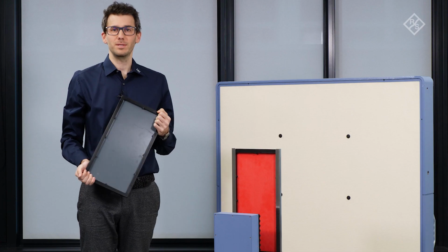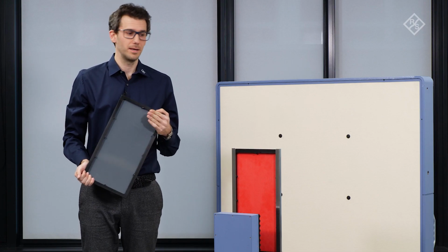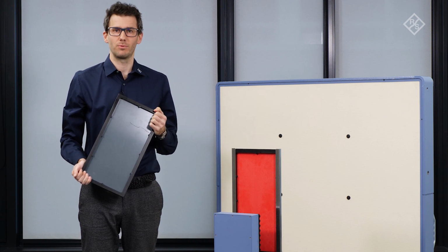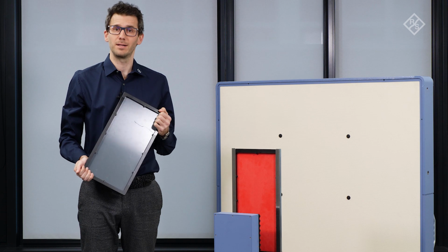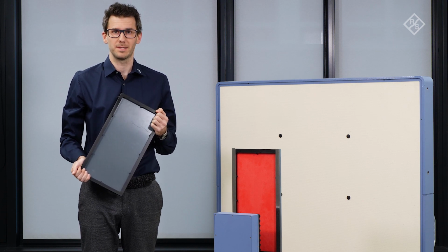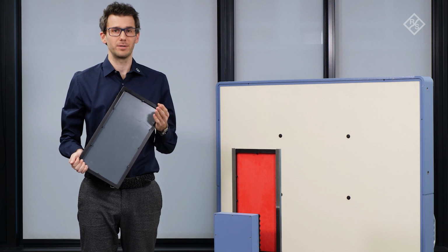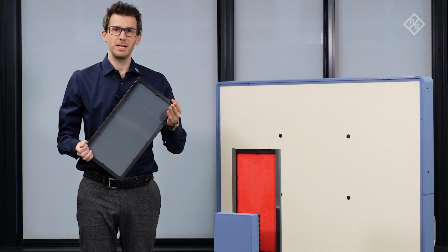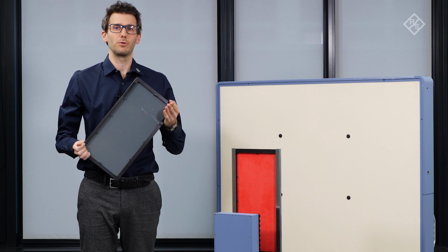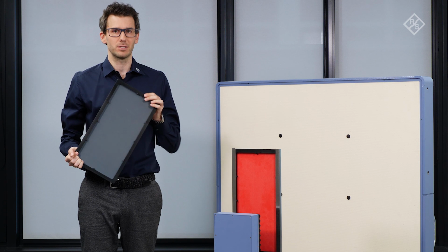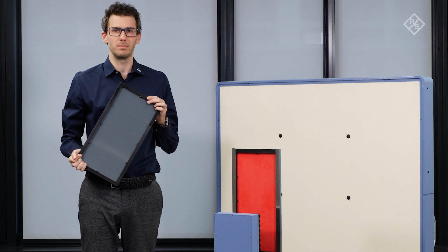So depending on the intention of the measurement, either the QAR-K10 software or the QAR-K50 software delivers the correct results. So using these two plates, the gray plate and the red plate, I would like to demonstrate how close the results captured with the QAR are to results captured with the VNA and a quasi-optical setup. These two plates have been characterized using a vector network analyzer. This plate came up with a reflection value of about minus 7.8 dB, while the red plate came up with a reflection value of minus 28.1 dB.